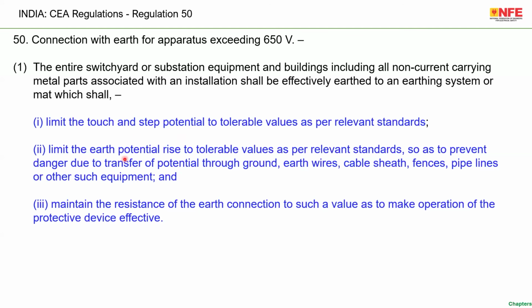Second requirement. Limit the earth potential rise to tolerable values as per the relevant standard so as to prevent danger due to transfer of potential through ground, earth wire, cable sheath, fences, pipelines, and or other such equipment. It means the earth potential rise, UE or EPR, has to be limited in such a way that on the low voltage side, transfer potentials are limited. Number 1 example of transfer potential is the voltage which is created due to the fault in the high voltage system destroying the equipment in the low voltage side of the transformer. Example, refrigerators in 25 houses burned, mixer grinders in 50 houses burned. So that is the second one.